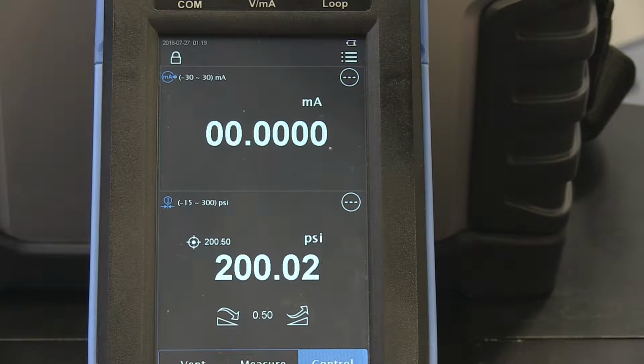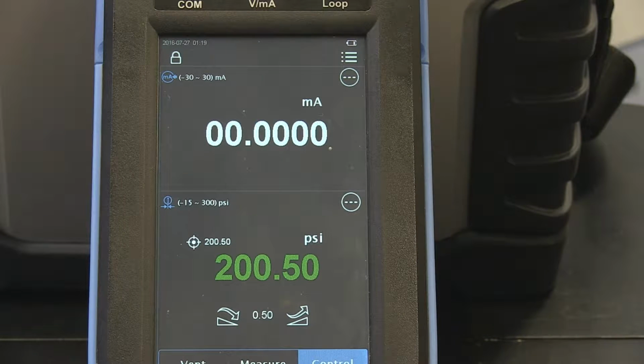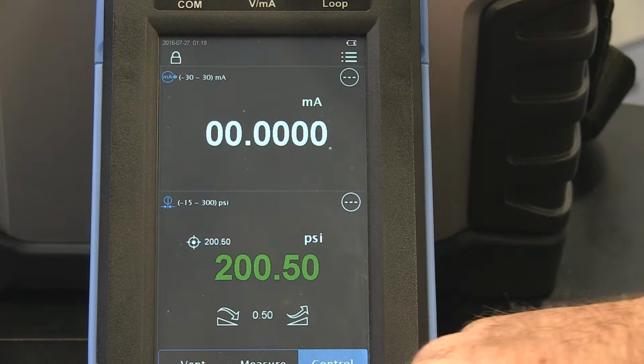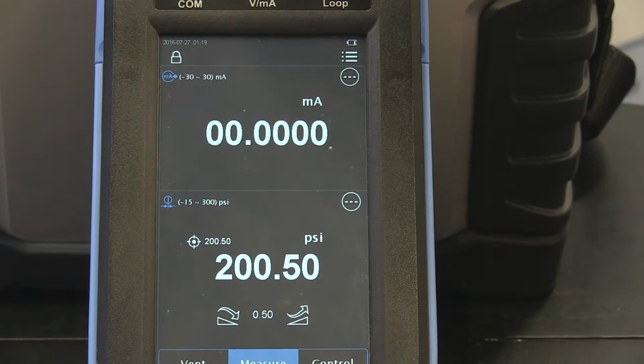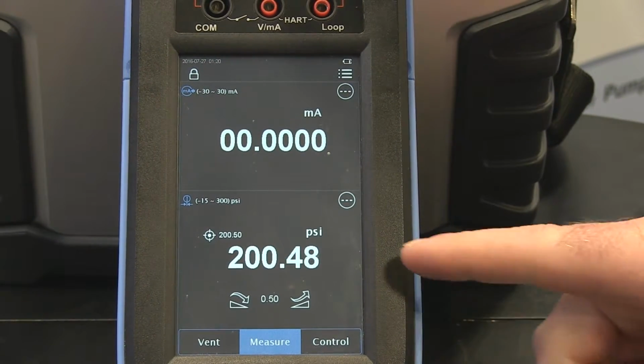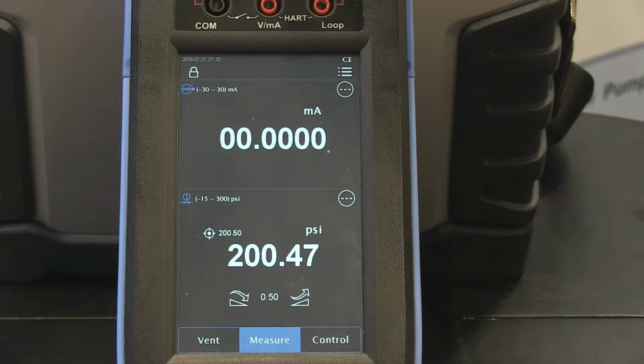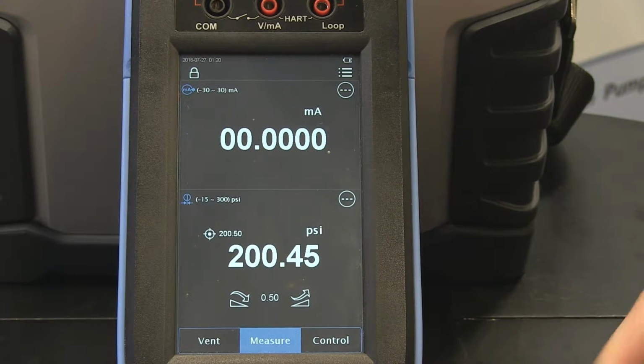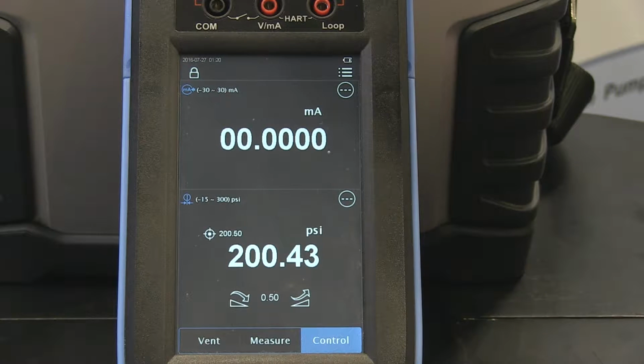If I want to go up, every time you hit that little arrow, it's going to bump it up by the amount of that step. So if you're trying to get a needle right on, you could just sit and continually bump that until the needle's on, and then take your reference pressure. You get your cardinal point, that's right. Vent is here, measure is here. If I want to just stick it in standby mode where it's not actively controlling. And then of course vent there. You can stick it back in control mode and it's going to go back to controlling.